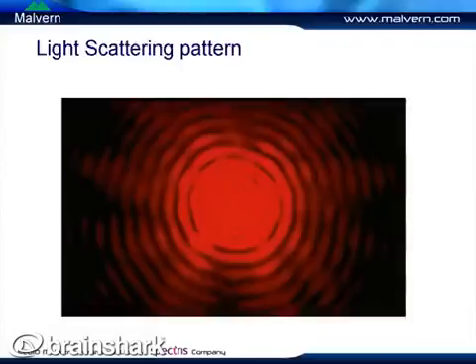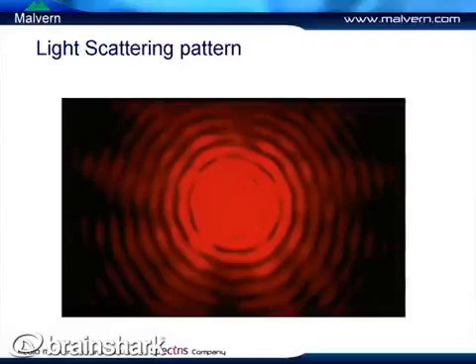Next, we'll look at a light scattering pattern — a diffraction pattern for some particles. This is the type of scattering we'll be measuring in the diffraction instrument. We'll have the laser essentially pointing in towards the screen, hitting some particles and measuring the scattering from them. The instrument measures the intensity of the scattered light as a function of the angle from the incident laser beam. Our diffraction instrument essentially takes a slice of cake out of this diffraction pattern — a triangular section — to look at how the intensity varies with angle.